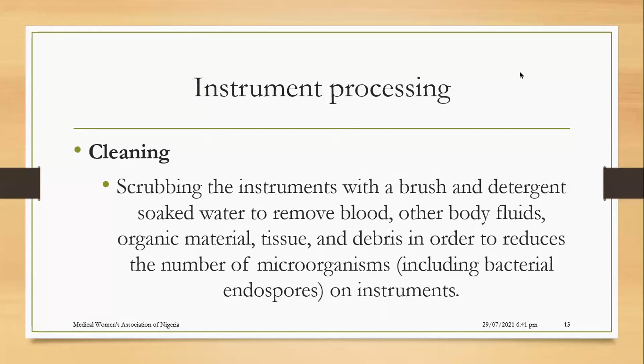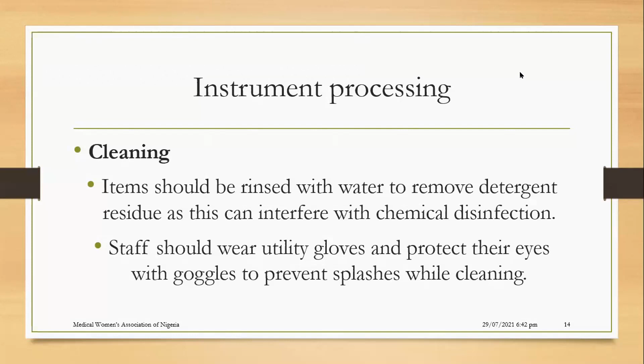Especially blood, once it dries, or if you have a lot of bleeding or body fluids, they tend to stick to the instrument. So that is not all. You need to clean it with a brush and detergent, and the health personnel doing it needs to wear protective gloves. After the washing, you should rinse the instruments with water, because if you are using chemical high-level disinfection, any residue of the detergent on the items will interfere with your chemical disinfection, which makes it suboptimal. So after brushing, ideally you should rinse very well under running water. The staff doing this should wear utility gloves and also protect their eyes from splashes while cleaning.